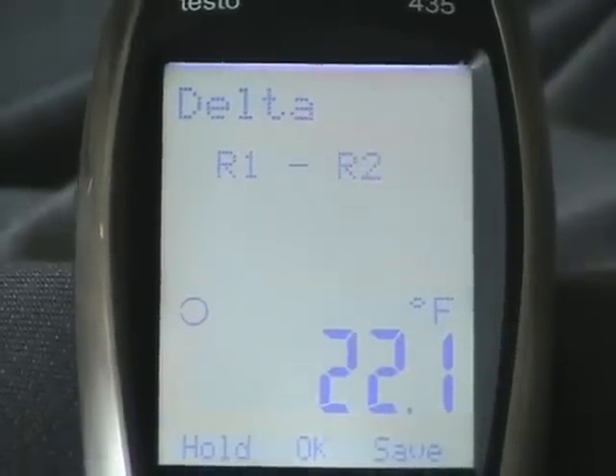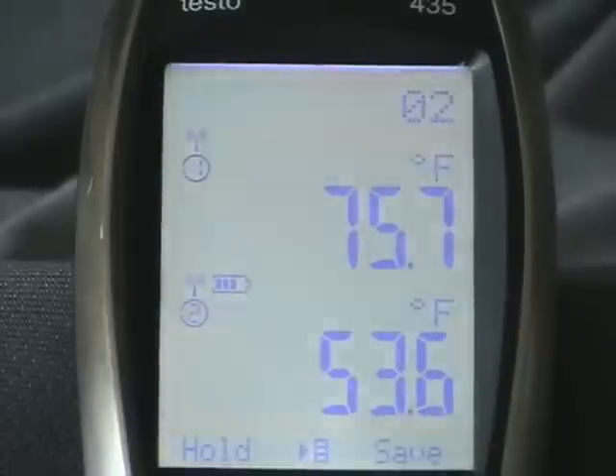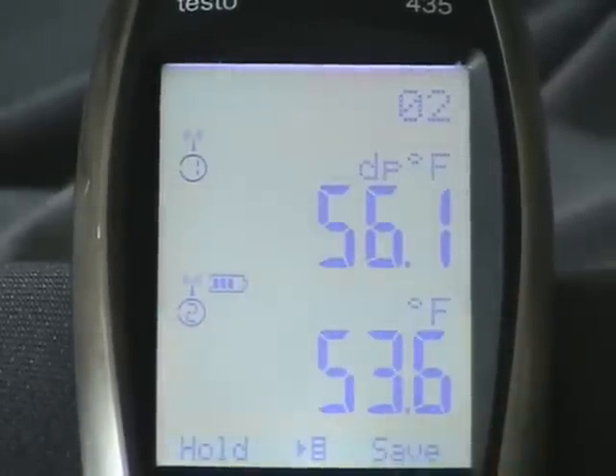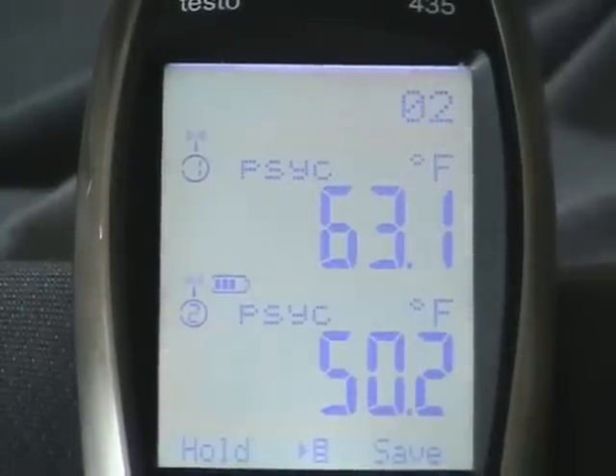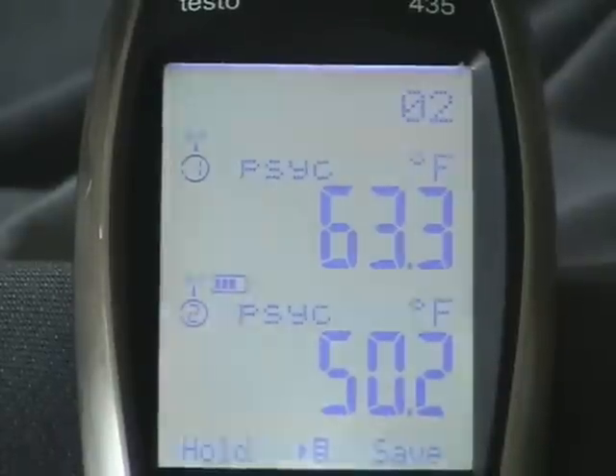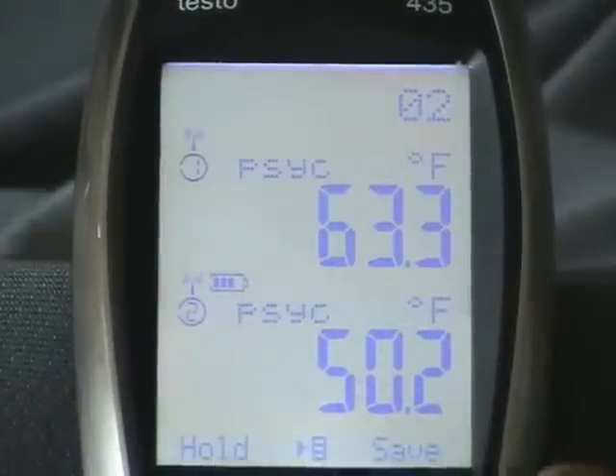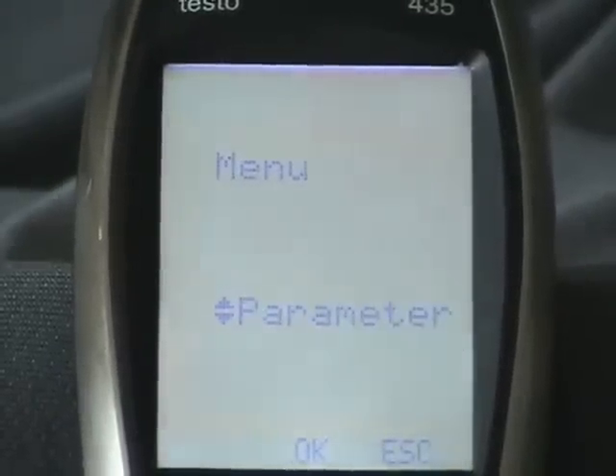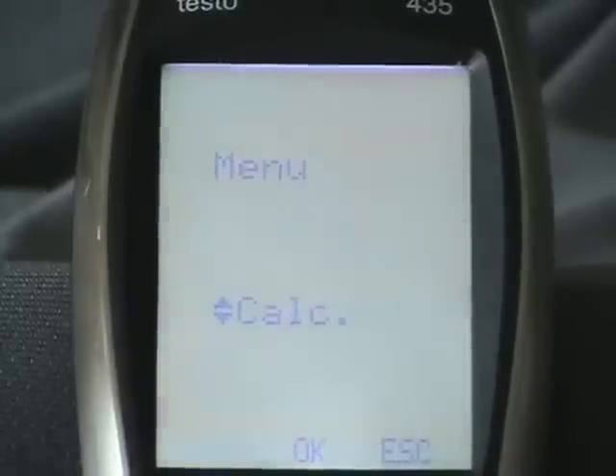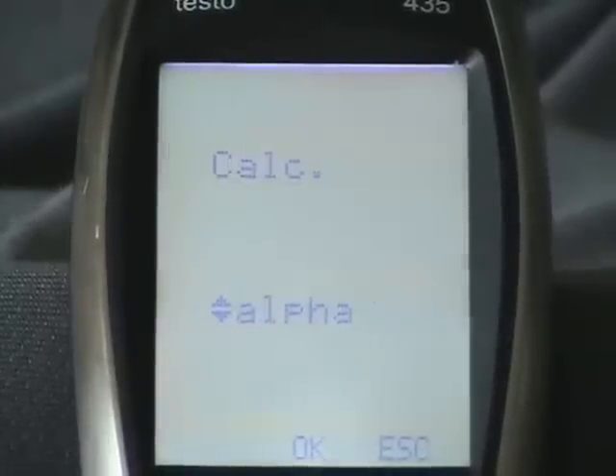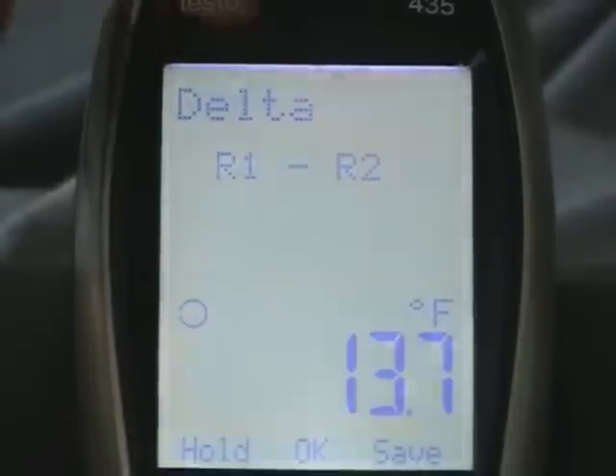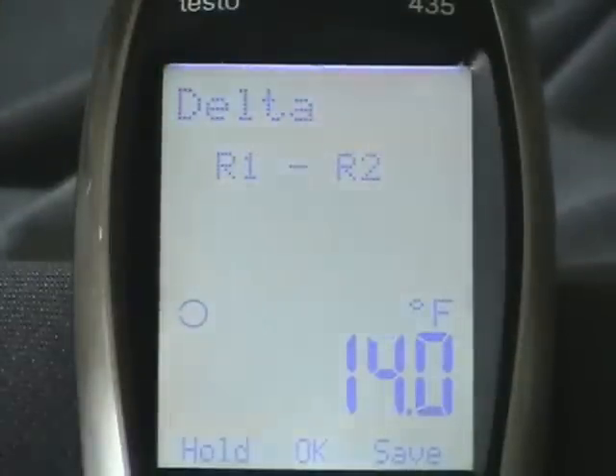Now, if you want to do wet bulb, for example, we go back to the main screen and we get the wet bulb reading, which is psych. So we got psych here, and we do the same thing — we hit the main menu, we go up to calculate, we hit okay, we go to delta, we hit okay, and now we're in delta mode. It's R1 versus R2, and this is our value.